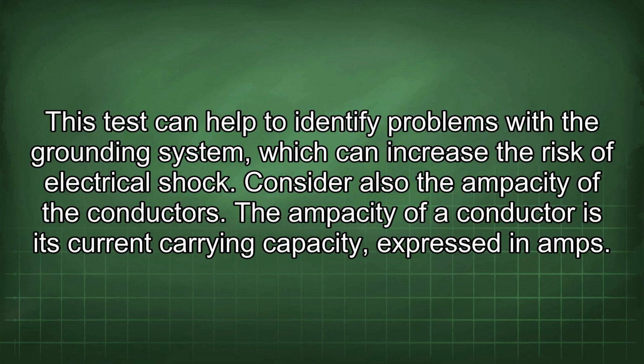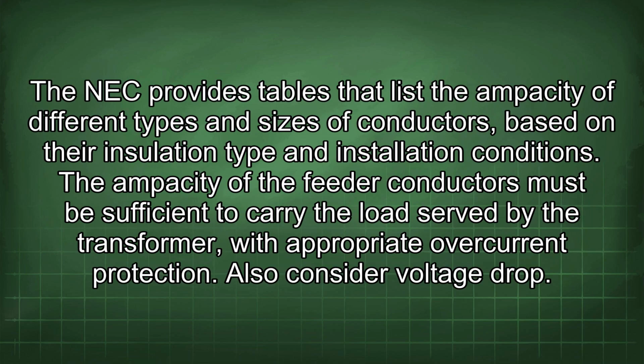Consider also the ampacity of the conductors. The ampacity of a conductor is its current carrying capacity, expressed in amps. The NEC provides tables that list the ampacity of different types and sizes of conductors based on their insulation type and installation conditions. The ampacity of the feeder conductors must be sufficient to carry the load served by the transformer with appropriate overcurrent protection.